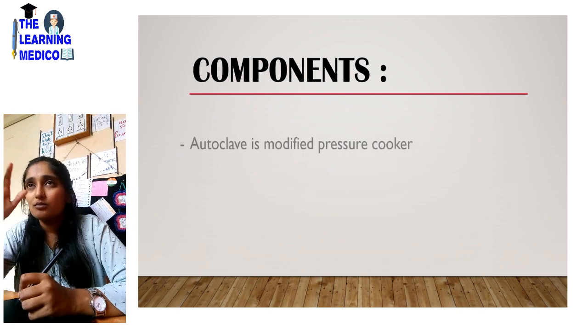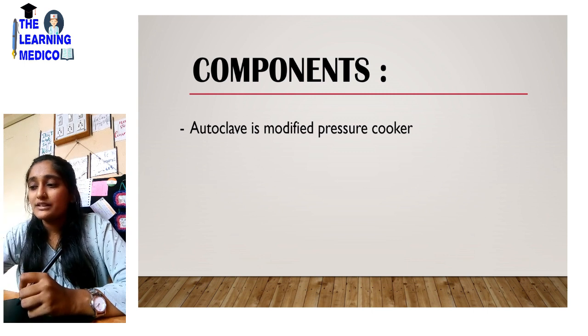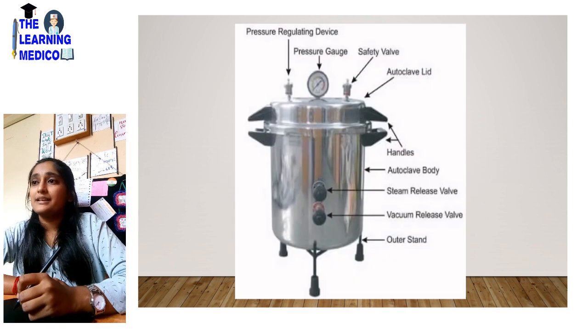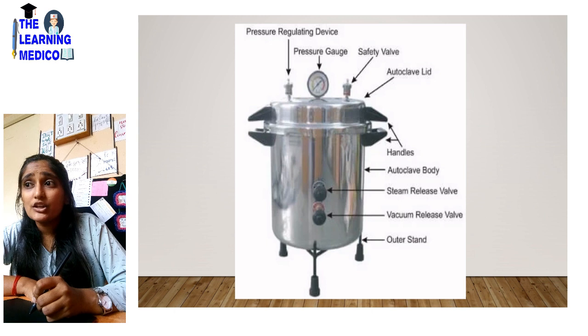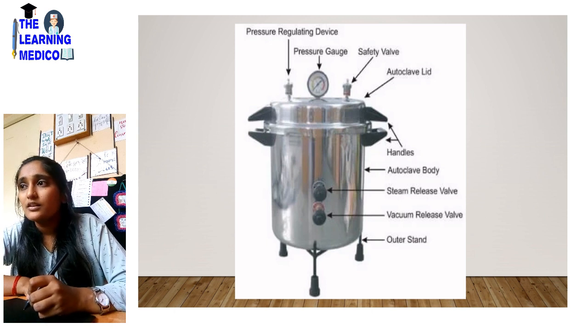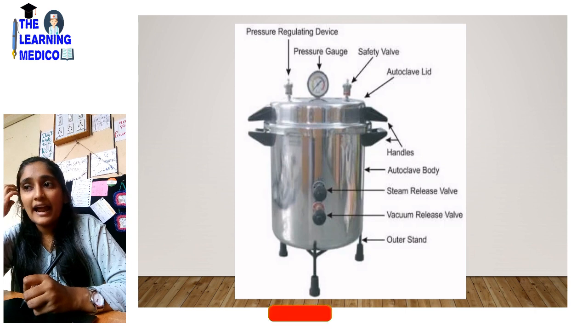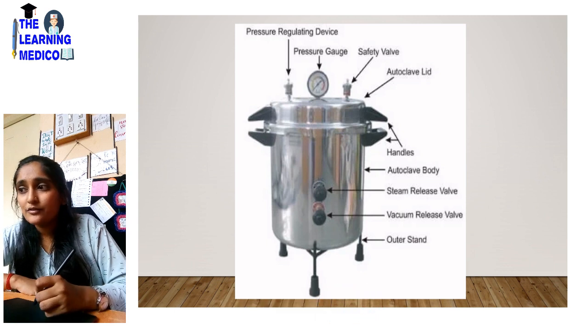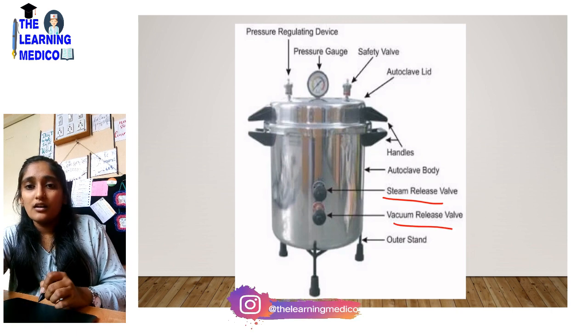Now, the components. An autoclave is a modified pressure cooker — very similar to one. It consists of a vertical and horizontal cylinder of gun metal. It has a pressure gauge to show the pressure inside, and a pressure regulating device. If pressure increases, there is a safety valve. There is an autoclave lid that makes it airtight, a handle, the autoclave body, a steam release valve, a vacuum release valve, and an outer stand.